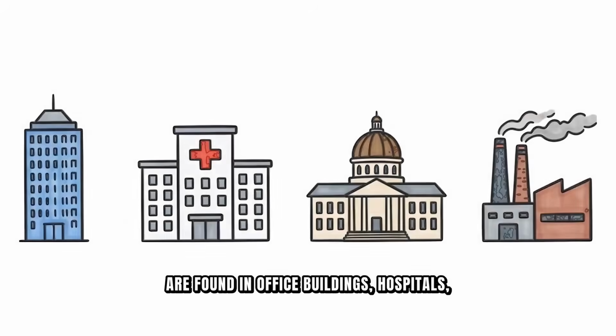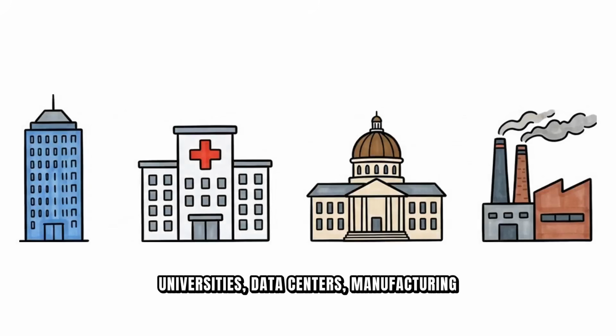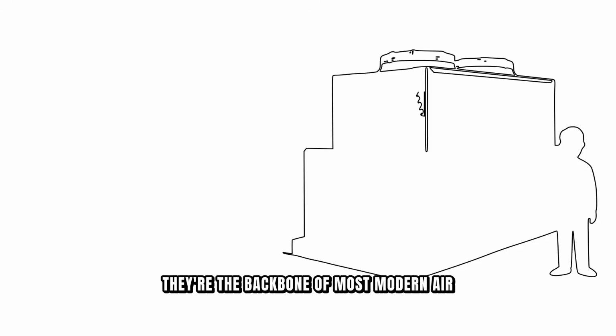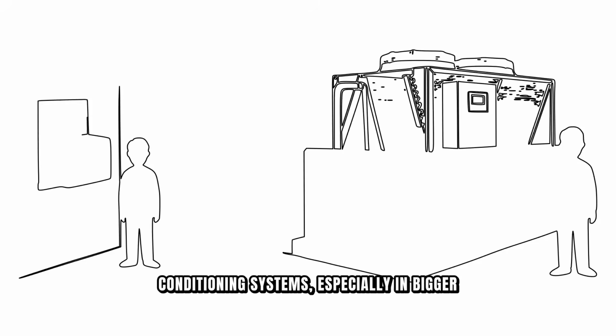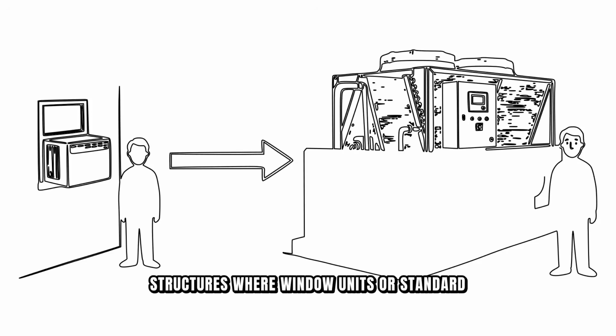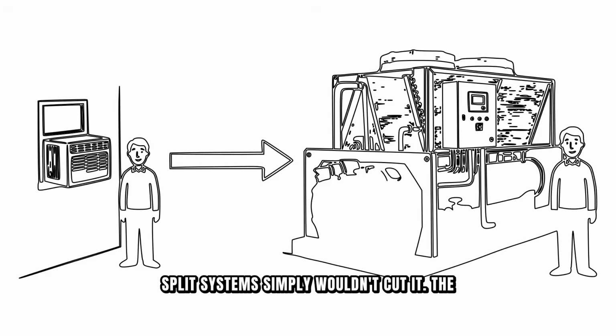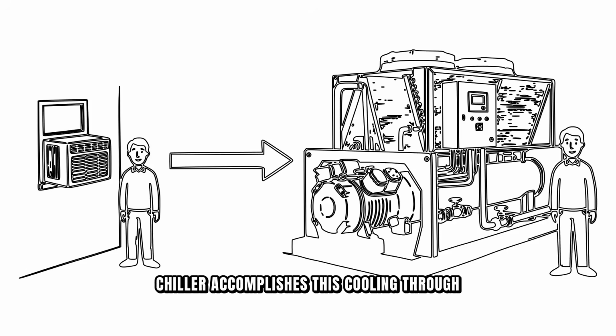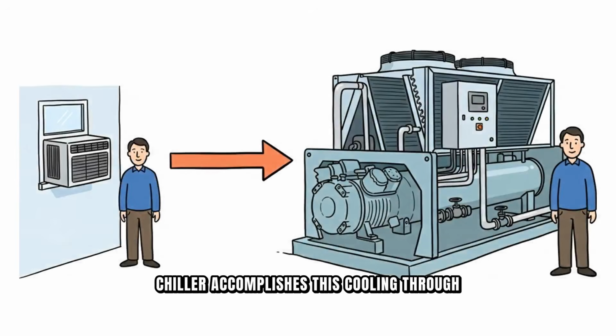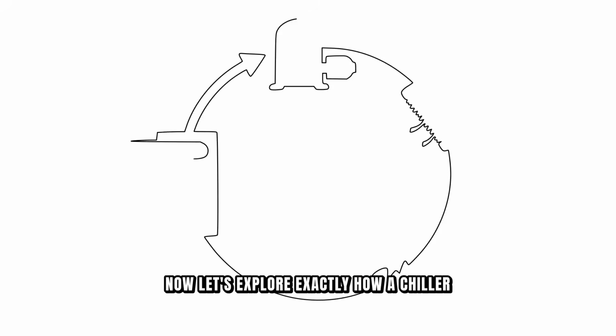Chillers are found in office buildings, hospitals, universities, data centers, manufacturing plants, and anywhere else that needs precise temperature control on a large scale. They're the backbone of most modern air conditioning systems, especially in bigger structures where window units or standard split systems simply wouldn't cut it. The chiller accomplishes this cooling through a process called refrigeration, which relies on the principles of thermodynamics and the properties of refrigerant chemicals. Now let's explore exactly how a chiller works.